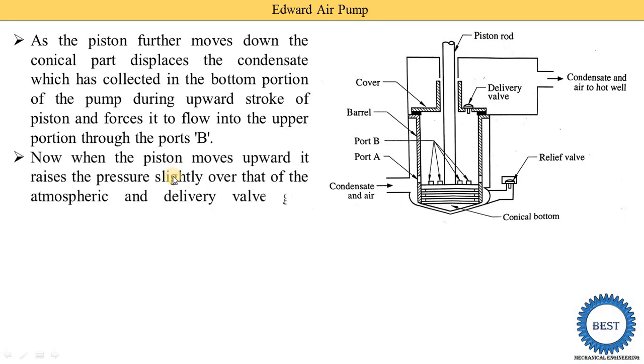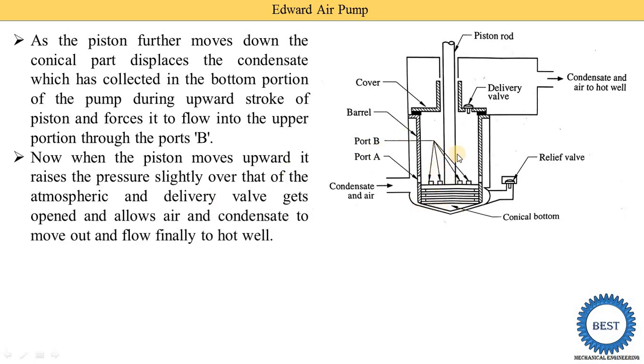When the piston moves upward, it raises the pressure slightly above atmospheric pressure. The delivery valve then opens and allows the air and condensate to move out and flow to the hot well. During the upstroke, condensate and air also enter the bottom part of the piston, and when the piston moves downward again, that air and condensate below the piston moves to the upper part through port B.